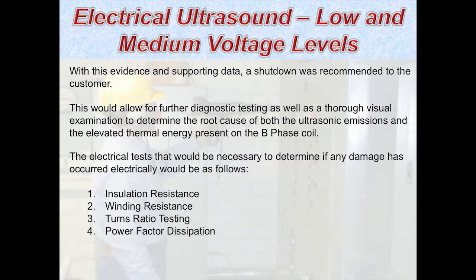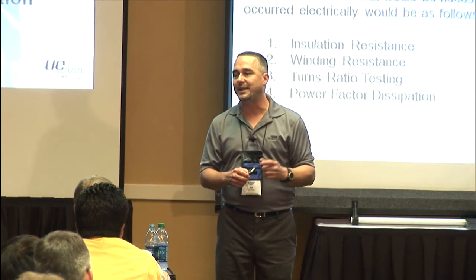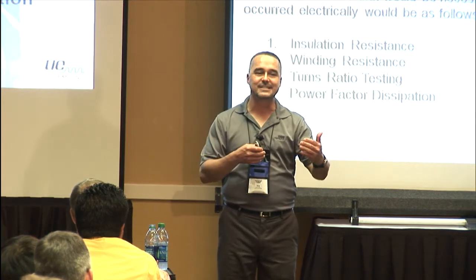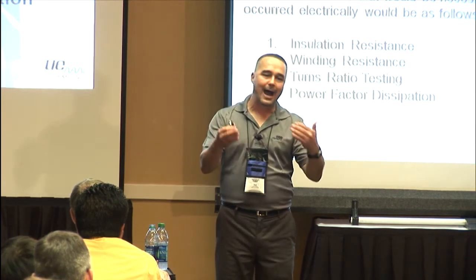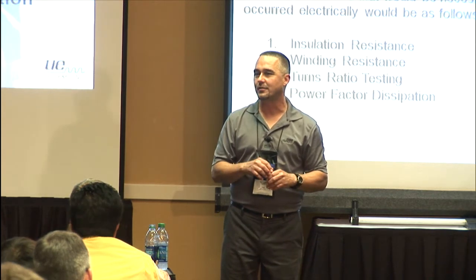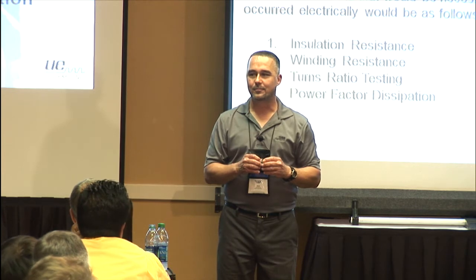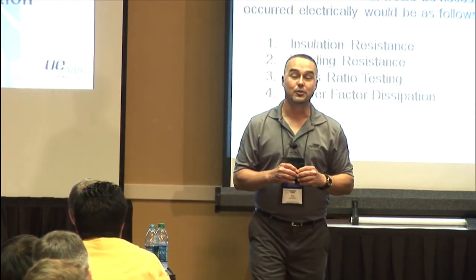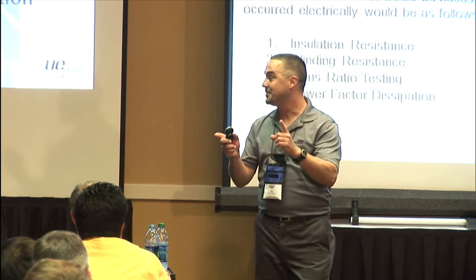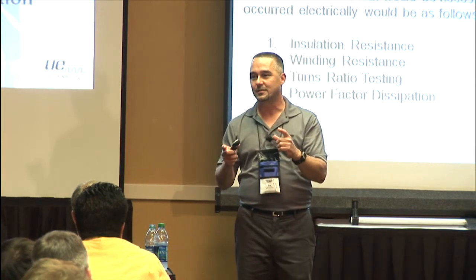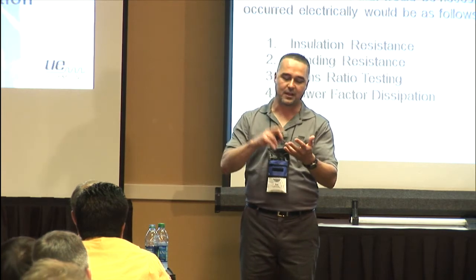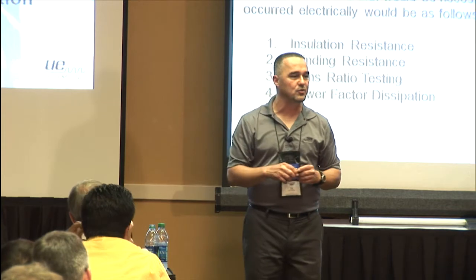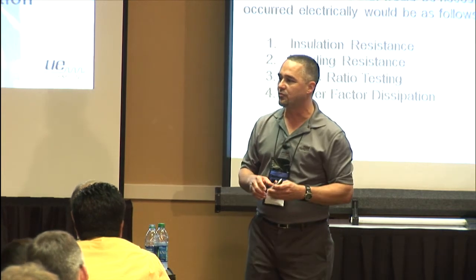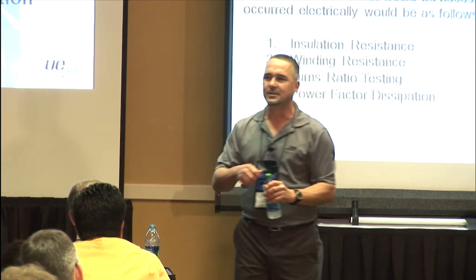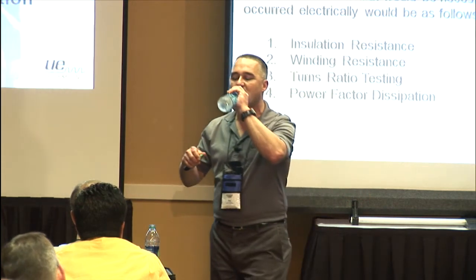Winding resistance is just to compare between the 3 coils on both the primary and the secondary phase. Do you have balanced impedances on the coil? If your impedances are not matched, how does that impact the operation of this device? Anybody know? Sorry? You'll lose your power factor for sure because the voltages and the currents become unbalanced. That can throw the phase angles off. That can also have a ripple effect all the way downstream into the system, and it gets exacerbated as it goes through all the components. So you get uneven heating and cooling, it just leads to a myriad of really nasty problems.